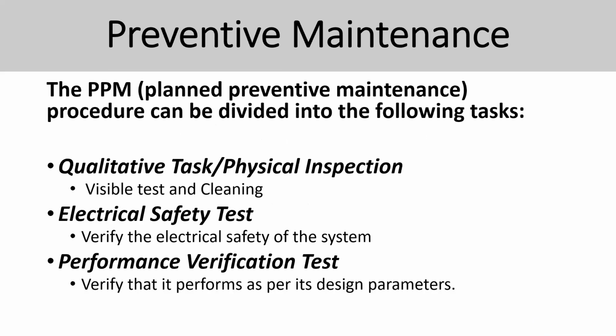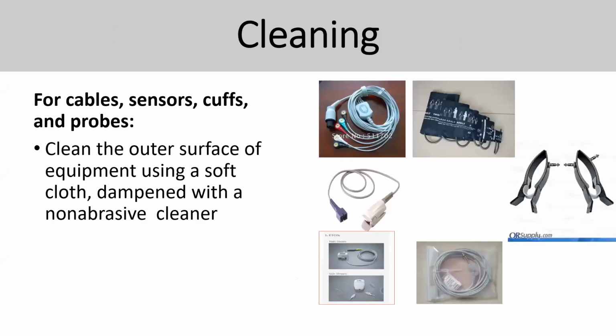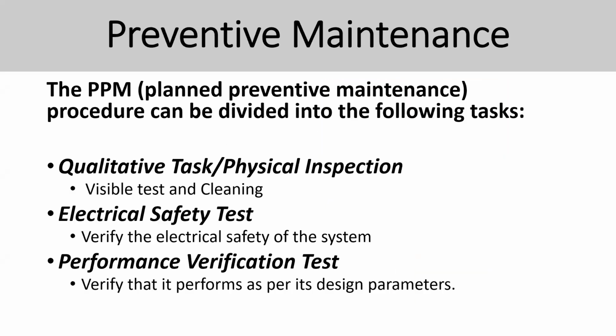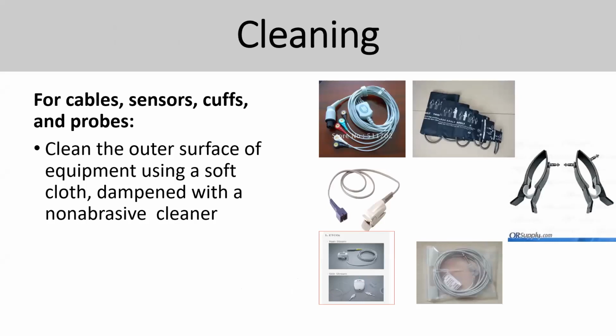So when you talk about preventive maintenance, you are talking about quality tasks like physical inspections, visible tests and cleaning, then electrical safety tests on the system, and performance verification tests. You're testing the parameter of each function like ECG, SpO2, whether it's working properly or not. To do that, you need to do certain things like cleaning. First thing, one of the important parts of it.